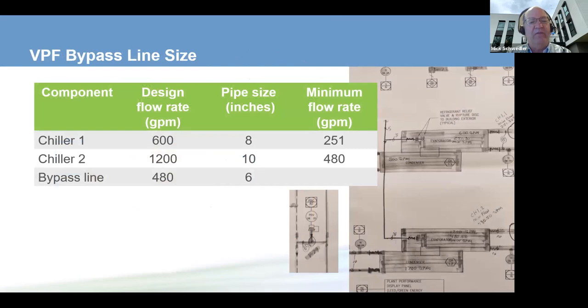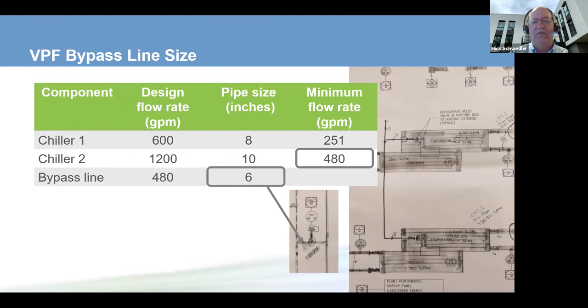So the pipe for the bypass line should be smaller than the pipe going into your largest chiller. So in this case, we have two different sized chillers. The minimum flow rate of the largest chiller is 480 GPM. That's a 6-inch line. We go to our drawing if we can find it. And there's our 6-inch line here. And we do have the right size line. So again, it's pretty simple. It's simple to find on drawings, a little bit harder in the field. But once you find that line, you can determine, is it the proper size?